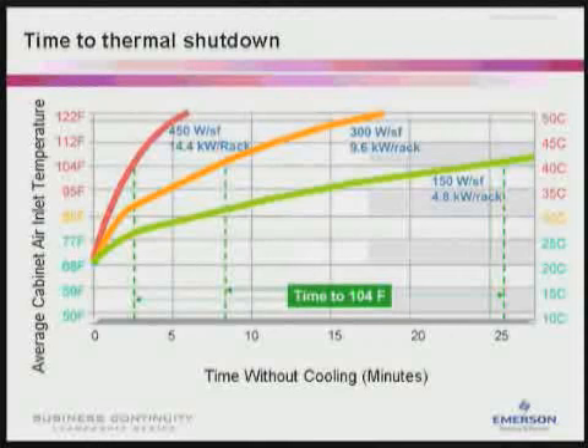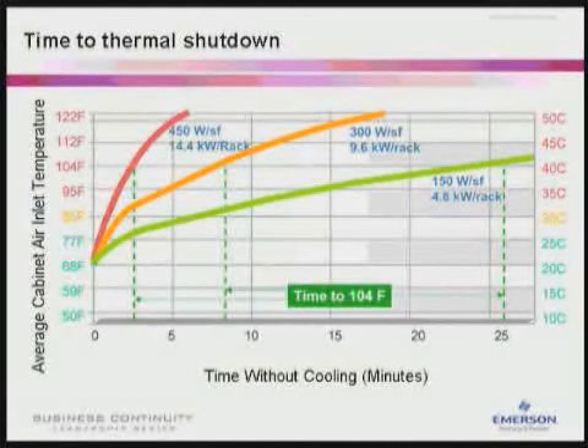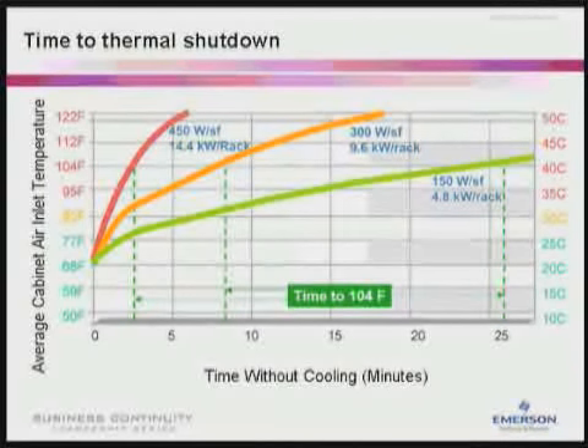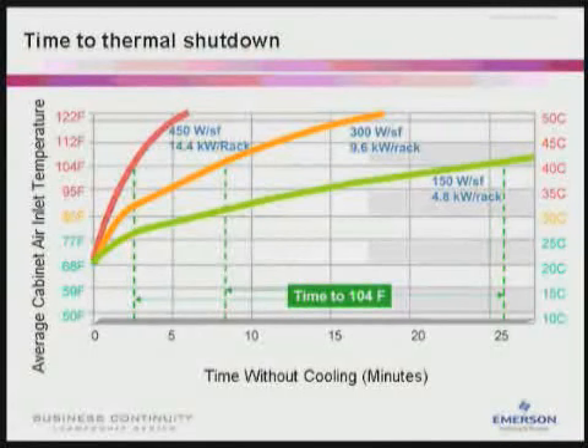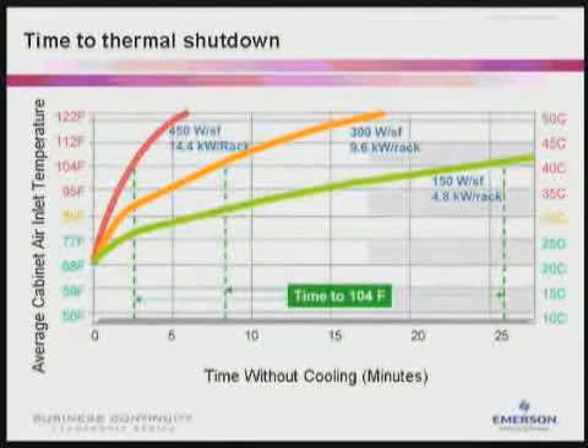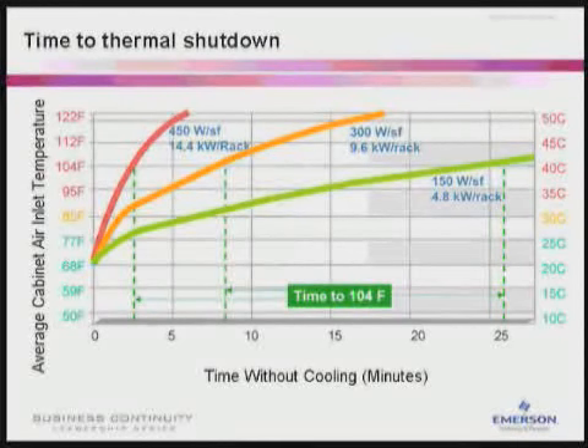Even if you aren't in a high heat density environment, an interruption in cooling can cause a failure. When one major New York area wireless service provider experienced system failure after the blackout of 2003, it was ultimately a cooling issue that brought them down. Though the power system, including batteries and generators, was designed for high availability, the cooling system was not attached to a backup power supply. So when utility power went out, so did cooling.